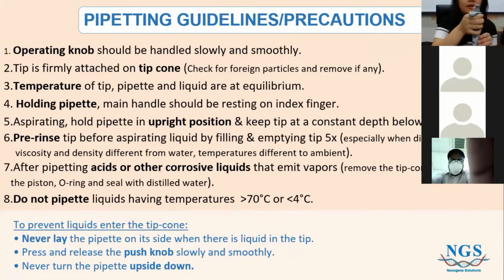When you're holding your pipette, make sure that the main handle is resting on your index finger, like this. When you're aspirating, hold your pipette upright, not slanted, and keep the tip at constant depth in the liquid. I would always suggest 1 cm below the surface of your liquid. One thing that a lot of people don't know is that you should always try to pre-rinse your tip before aspirating liquid. For example, you can fill it and empty it 3 to 5 times before you actually aspirate and move your liquids around.